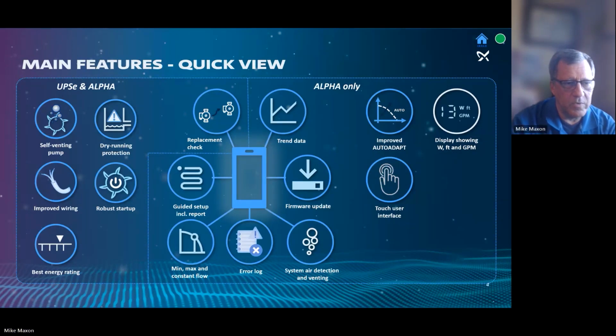So both pumps have the self-venting. Remember, the old pumps had the little vent screw on the back end. You'd open it up to get water into that rotor can. We don't have that anymore, but we ensure that the water will get into the rotor can. That's self-venting. They both have dry run protection, the robust start. They both have the improved wiring. We're talking about the UPSe and the Alpha here. And they both have the best energy rating on the market.